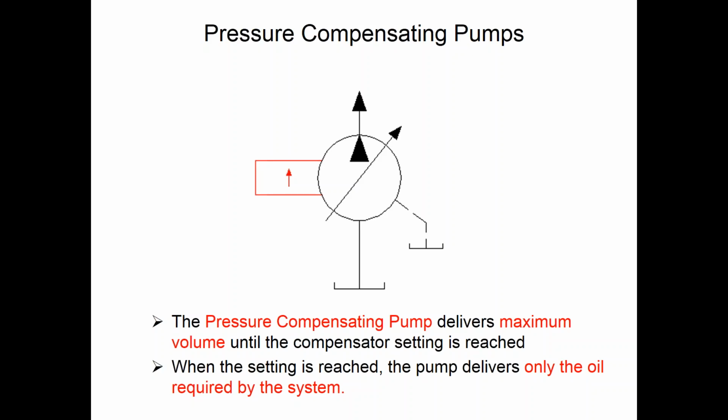With a variable displacement pump, since it varies its flow and it goes anywhere from 0 to full flow, then it's entirely possible that this pump could be bypassing more than it's delivering. That means the fluid has nowhere to go that bypasses across the tight tolerances. It gets stuck there in the pump case, and pressure would build and blow out the shaft seal. So that bypassed oil gets delivered back to tank through the case drain to keep pressure from building against the pump shaft seal. Right.